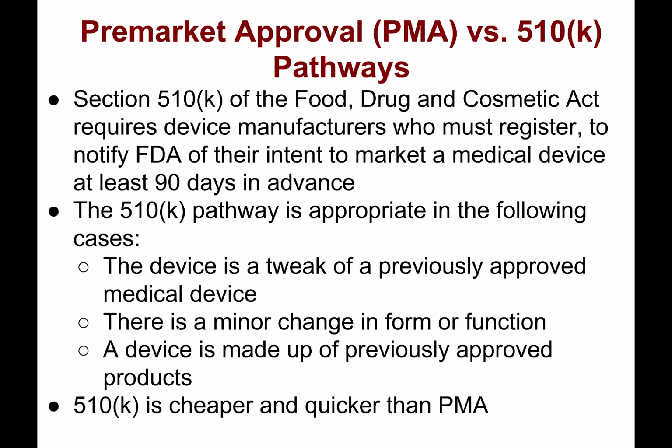The 510K pathway is actually a reference to a section. It's section 510K of the Food, Drug, and Cosmetic Act. And it requires device manufacturers who must register to notify the FDA of their intent to market a medical device at least 90 days in advance.